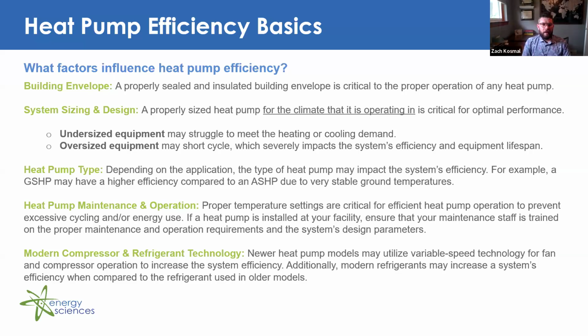So just to reiterate that, say for example, your facility is only occupied Monday through Friday, and you have traditional HVAC equipment where on a day like today, you may have your thermostat set at 75 degrees. And then once Friday afternoon comes along, that building is no longer occupied for the weekend. You may increase that temperature set point to 80 to 85 degrees, just to relieve some of that load on your HVAC equipment during those unoccupied hours. You do not want to do these setbacks or setups with heat pumps, okay? And if you do want to implement a modest setback of 2 to 3 degrees, that should be something you would want to mention during the equipment design to make sure that it is designed for that application.